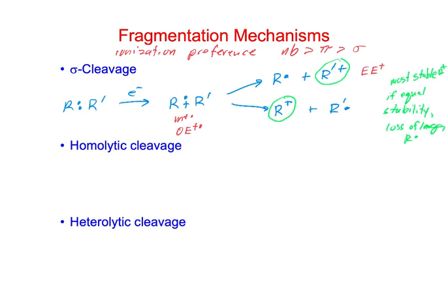It goes out from the instrument? Yeah, the radicals, because remember in EI, we're doing this under high vacuum. We have a vacuum pump that's pumping it out. So anything that we don't observe, there can be other things formed. We could have anions that are formed in the process or neutral species. Any of those will just be pumped out. Only the cations get accelerated down the flight tube. All of the cations will be accelerated, so these will all be observed.